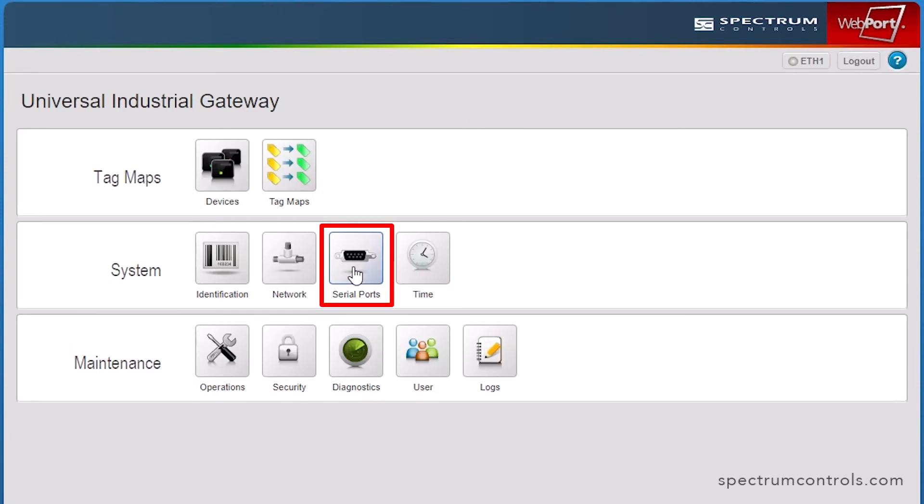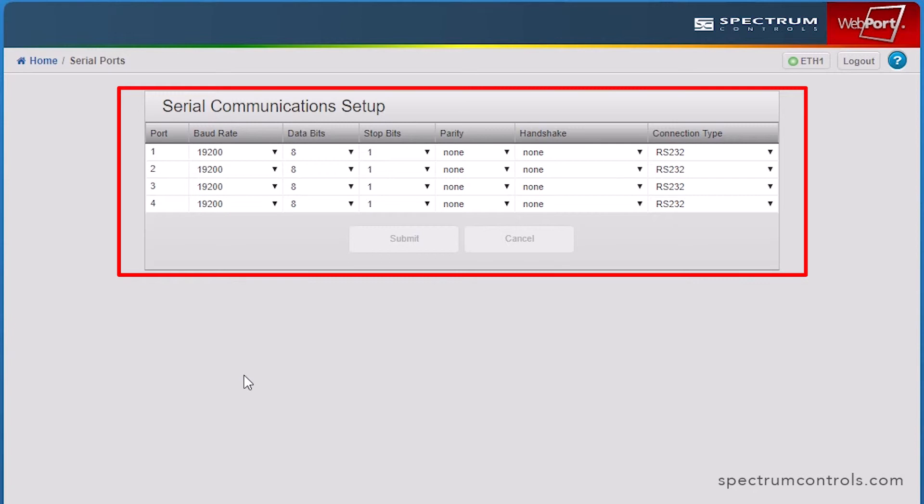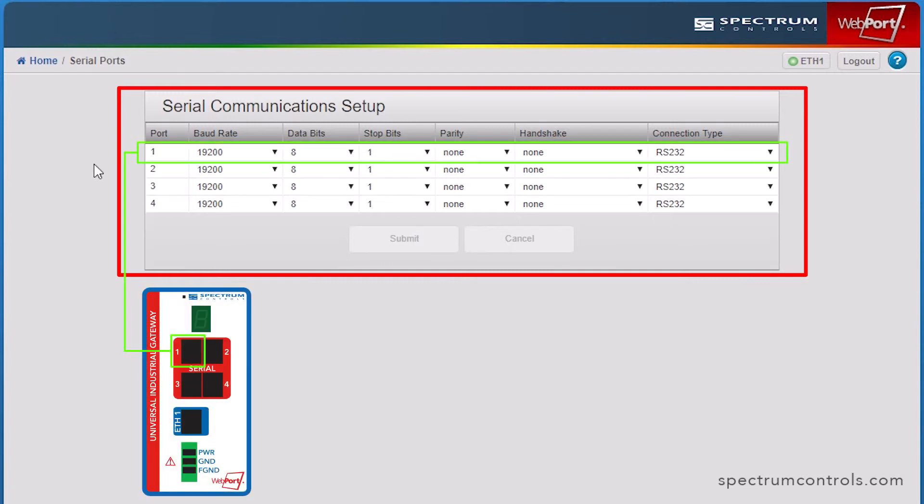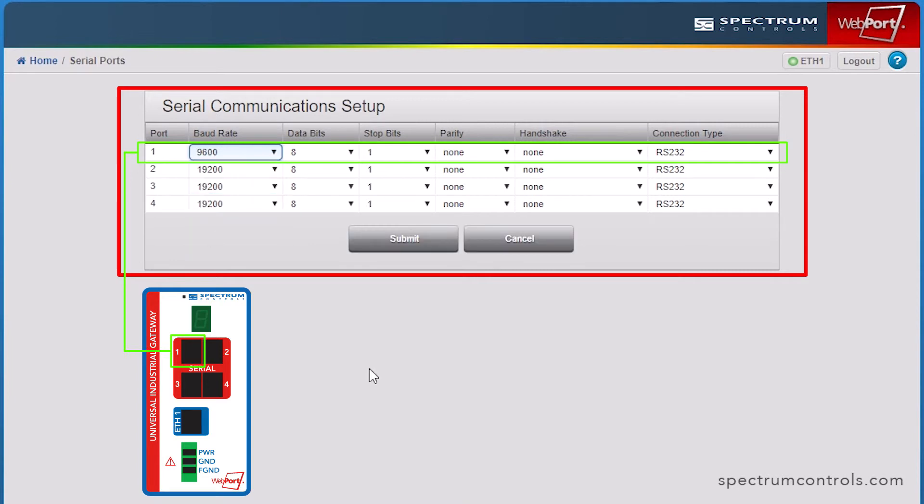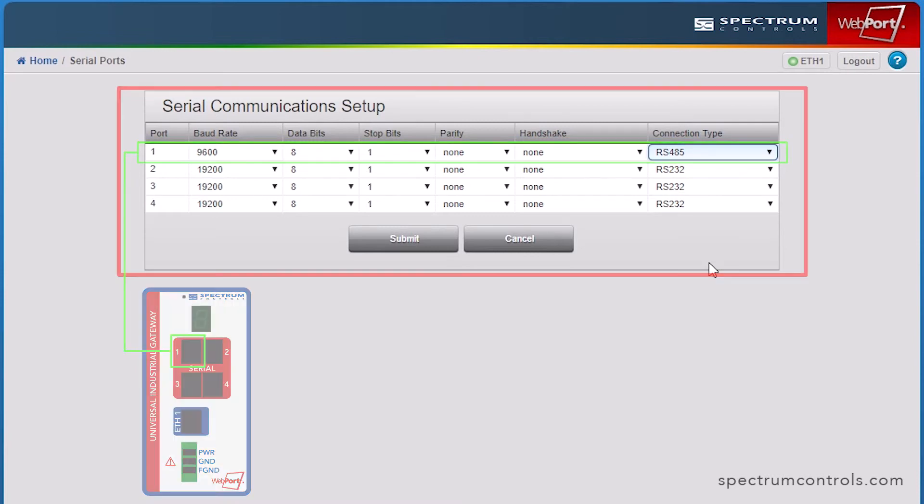Now, select the Serial Ports icon. If you are connecting a serial device to your gateway, configure the appropriate serial port on the gateway to match the configuration of the serial port on the device being connected. Both RS-232 and RS-485 connection types are supported. Click Submit.